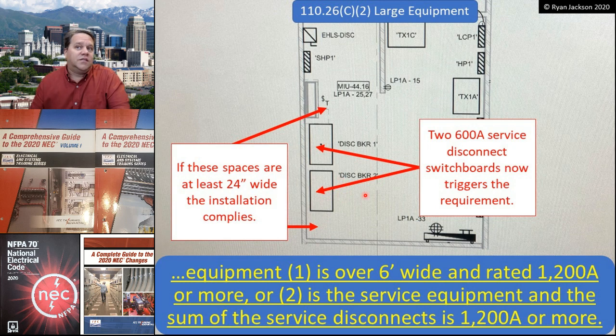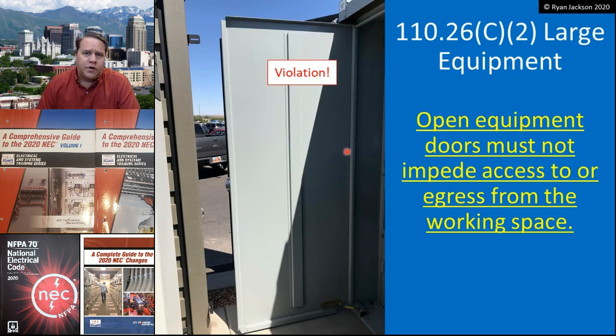Now this installation as drawn complies. In fact, we could make this much worse and still comply. Let's imagine this wall extends all the way to the other wall here, all the way down. It would still comply, because as I'm looking at this equipment, if I turn to the left, I can escape into a 24-inch wide space. As I'm working on this equipment, I can turn to the right and escape into a 24-inch space, so I'm good. Now listen, there are better places to be if this equipment is blowing up. There are better places to be than down here in this corner. But there's a lot worse places to be, and that would be right in front of the equipment. All we're trying to do is get it so you're not in front of the equipment if something goes wrong. Now again, most of that didn't really change. The only change here is the service disconnect, 1200 amps, sum of the disconnects change. The big change is 110.26(C)(2).